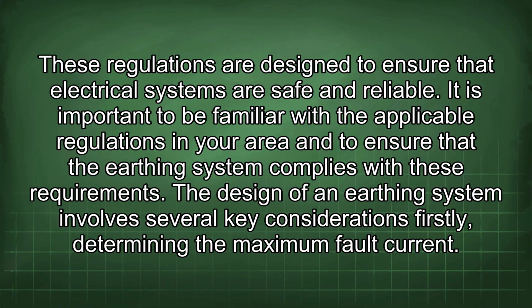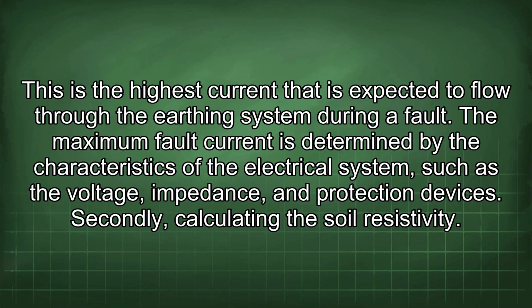The design of an earthing system involves several key considerations. Firstly, determining the maximum fault current. This is the highest current that is expected to flow through the earthing system during a fault. The maximum fault current is determined by the characteristics of the electrical system, such as the voltage, impedance, and protection devices. Secondly, calculating the soil resistivity.